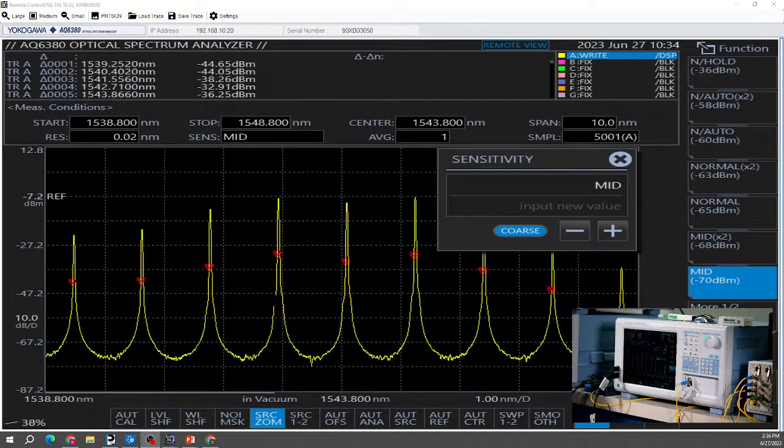We have been asked about having a faceless unit, meaning just a box with no display and buttons. It turns out the display was really a small part of the cost of the whole instrument, so it didn't really save much cost. The remote command is already there, and I know some people may be concerned about people touching the buttons, and that can be locked out too in production. That is what we used to address that issue quite effectively over the past few years.